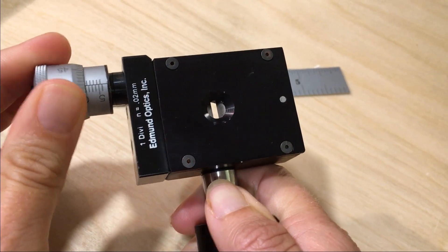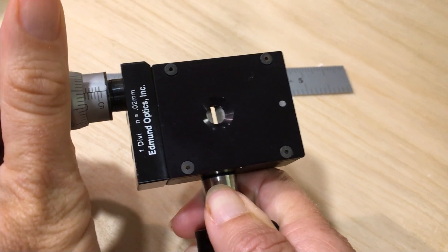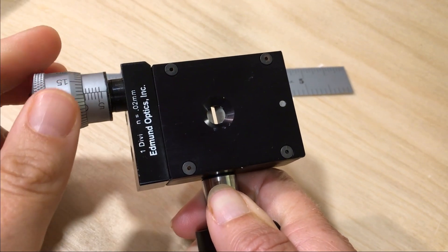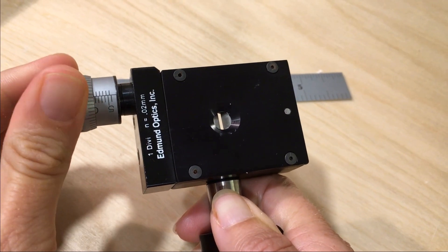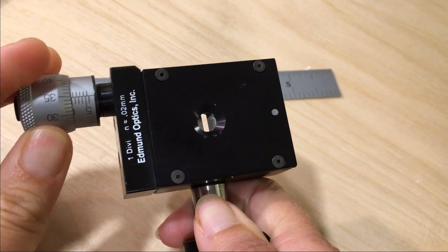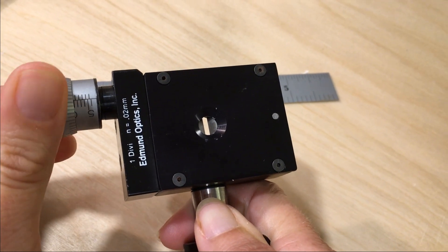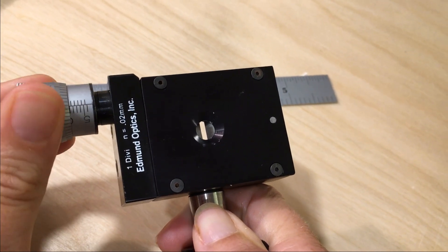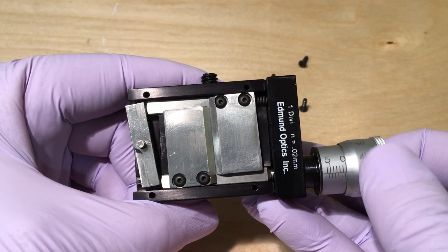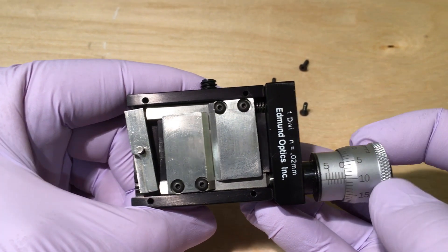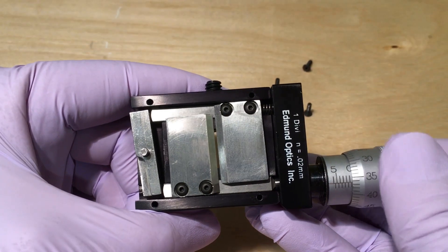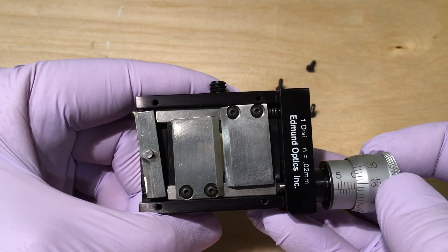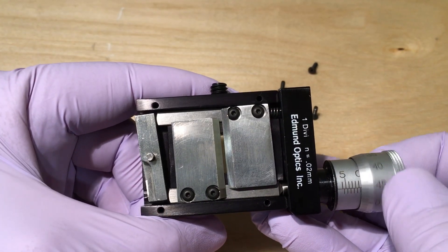We can feel backlash in turning the mechanism in alternating directions, so we're particularly suspicious about the performance at small widths. We also don't know the extent to which the center of the slit stays constant as the aperture is changed. The internal mechanism moves the left and right jaws in equal and opposite directions with a precision micrometer, so the biggest calibration error is likely the zero offset.